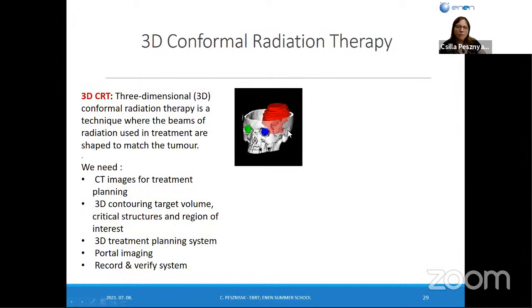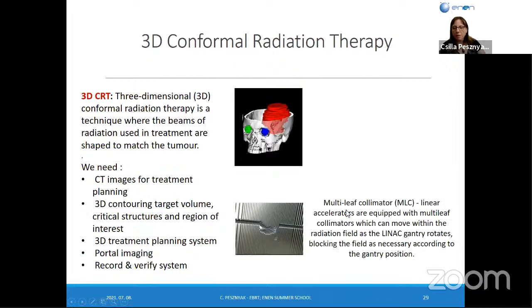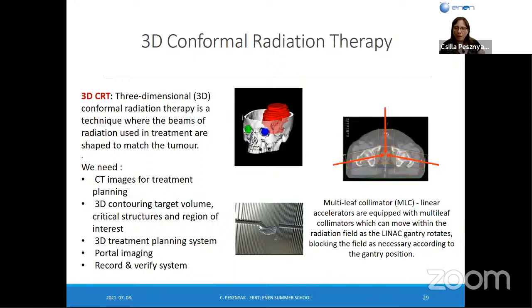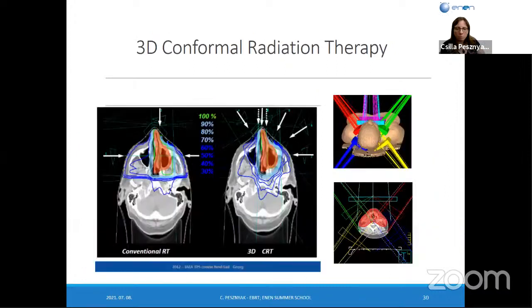The conformal radiation therapy uses the 3D reconstruction of the target. We have here the MLC, multi-leaf collimator, and in this way we can change the shape of the beams. And we use the SAD technique, source axis distance. We need to set up only one point, and all movement of the accelerator and table will be around this one point. Here are some conformal plans.